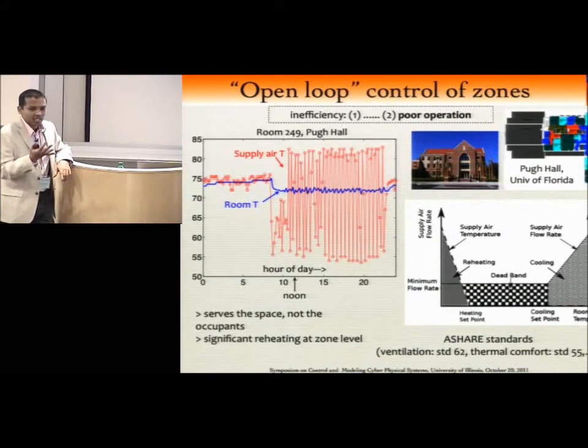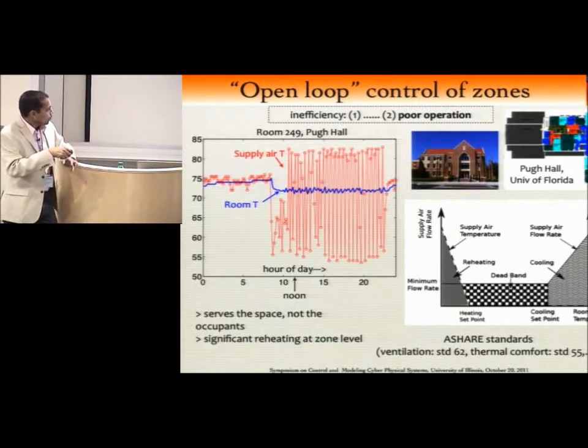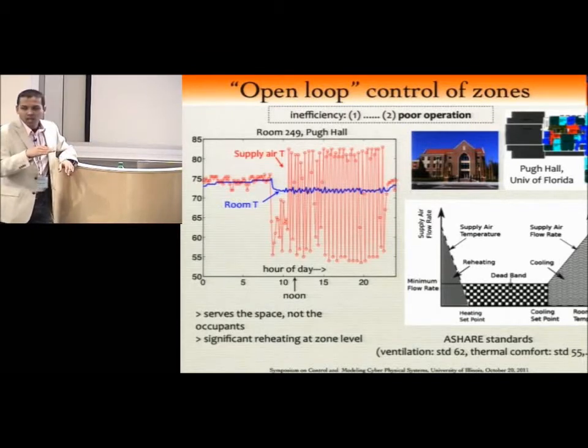As I said earlier, there are two things you can control, right? Either the flow rate or the supply air temperature. So it looks at the temperature, and if the room temperature is between a high value and a low value, a cooling set point and a heating set point, that's supposed to be the comfortable range, more or less. It supplies the minimum allowable amount of air, and that minimum is dictated by standards, mostly by ASHRAE standards. ASHRAE stands for American Society of Heating, Refrigerating and Air-Conditioning Engineers. They tell you what you can or cannot do in a building. So it supplies the minimum amount of air as long as the temperature is between these high and low points.